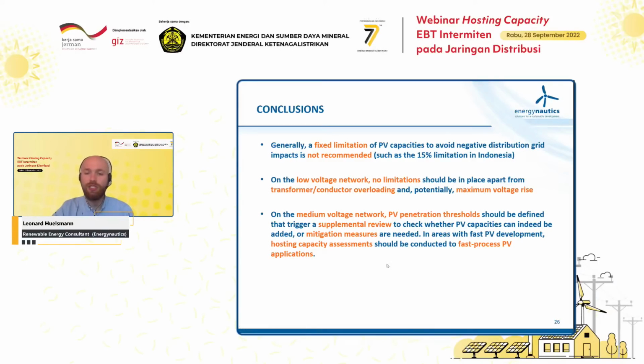Certain thresholds should be defined that trigger a supplementary review. In the US, this threshold is defined as 15% of medium voltage peak demand. This triggers a supplemental review, which doesn't mean it's limited to 15%, but only that a more detailed study is potentially carried out, or that it is compared to the hosting capacity of that specific feeder. This ensures that you can fast process these PV applications - you can just make checks and compare with some numbers without doing a very detailed power system study that would otherwise be required.